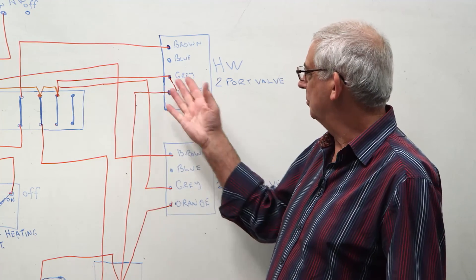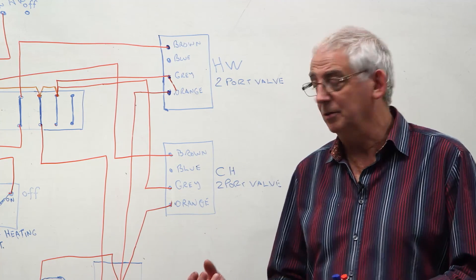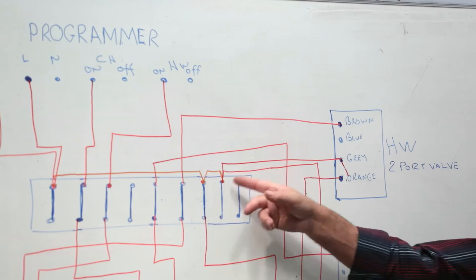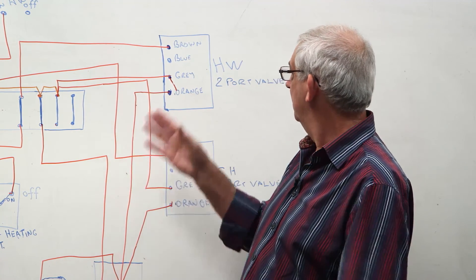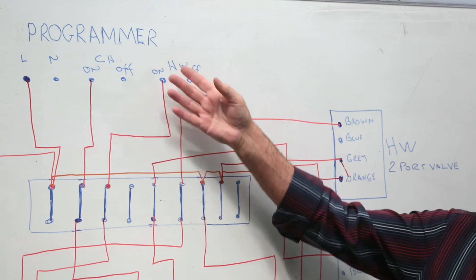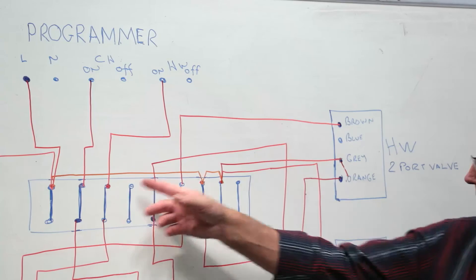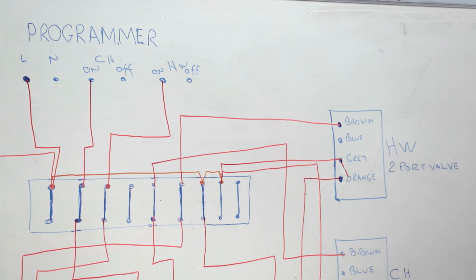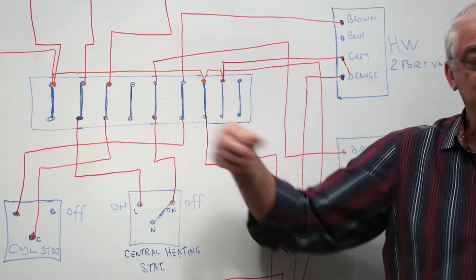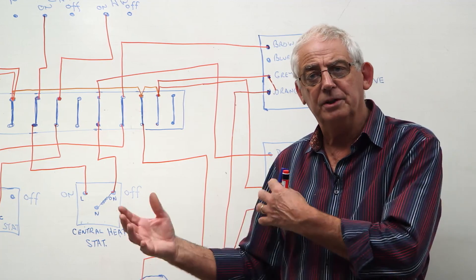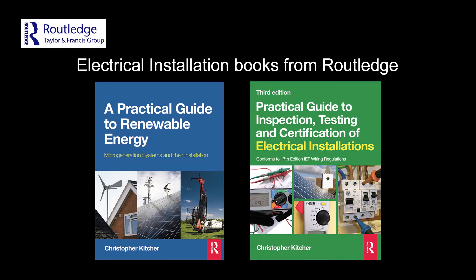As already explained, the grey cable of the motorized valve needs to be live when the central heating or the hot water is calling for heat. For my grey, I've just gone to a permanent live, which is fine. It'll work perfectly well. You could also, if you wanted to, of course, for the hot water two port valve, just connect it to the on of the programmer. So, when the programmer is calling for heat for the hot water, the grey becomes live. The same would apply to the central heating. I've got a permanent live to my grey, but of course, I could, if I wanted to, connect it to the same connection as the on terminal for the programmer. Whichever way you do it, it's still going to work. The choice of how you do it is entirely down to you.